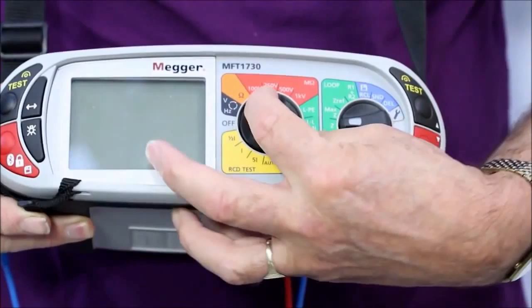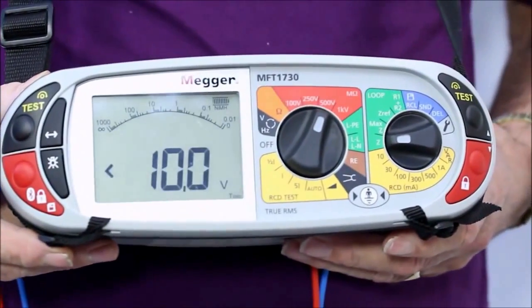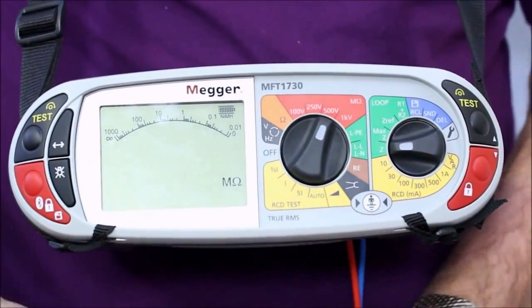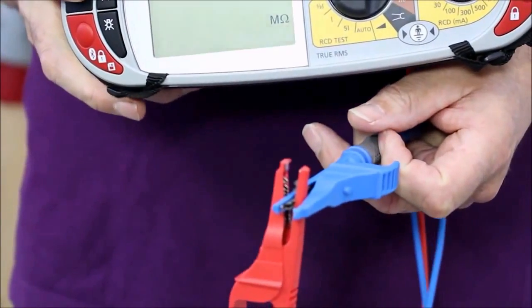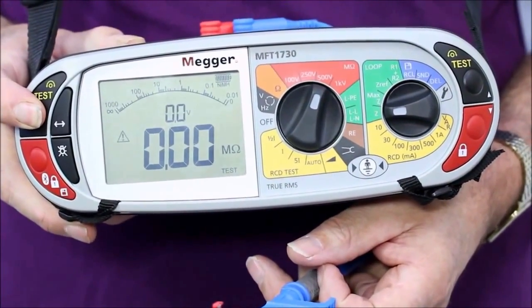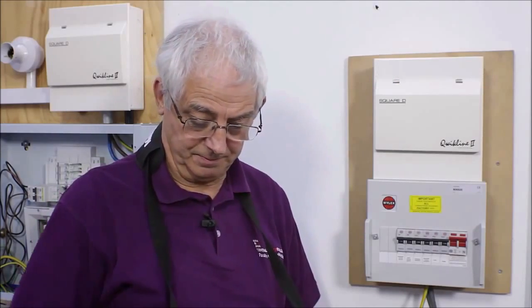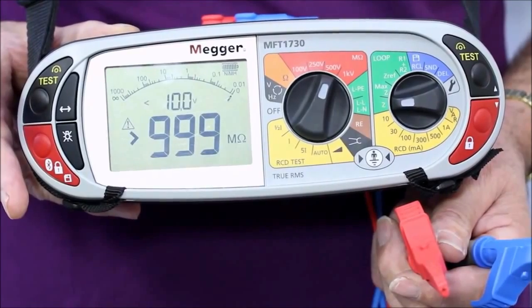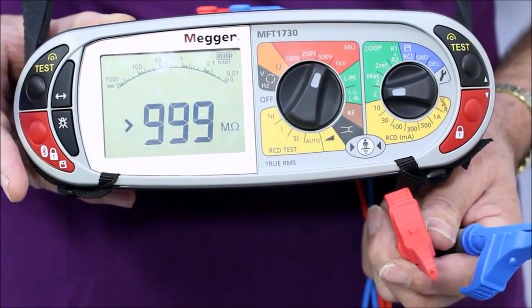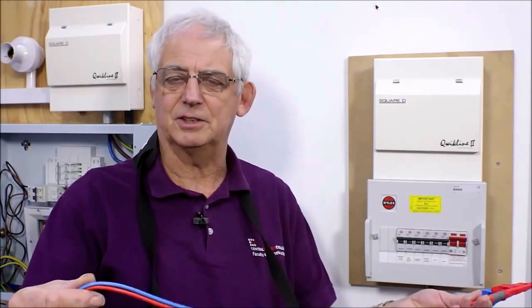Next thing, I use an insulation resistance tester. This is a multi-function instrument, but all I need to do is turn it on to 500 volts because this is a 500 volt DC test. I've got to make sure that the tester is working properly. So I need to join the leads together, push the test button, and I should get a reading of 0. Take the leads apart, push the test button, and it should be over range, and this meter goes to 999 megohms. Once I'm sure the instrument's working properly, just one final check is to make sure that the leads are to GS38. Obviously, it's a 500 volt test, and anything over 50 volts, the leads do need to comply.